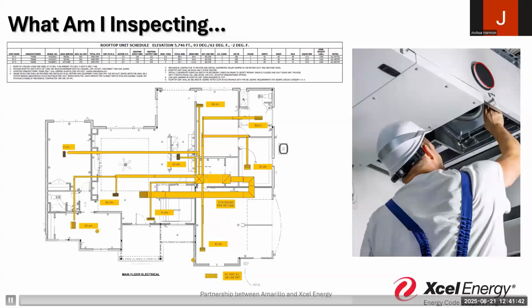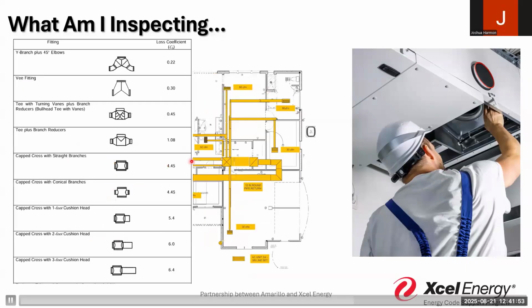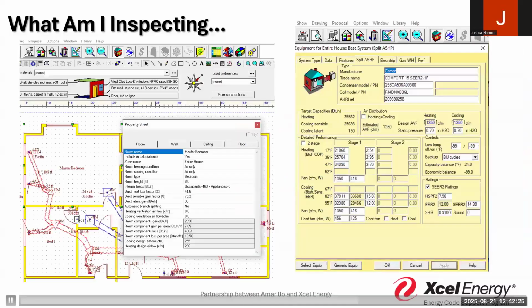It takes time to get that understanding within our designers that I want to know not only the CFMs of air going to each vent in those different rooms, but also what those different fittings, boots, and terminations are going to look like. I can't tell you how many times I'd go out there and think, I know there's supposed to be a T here, is it the right T? Is this the right Y? Is this the right 90? All I know is that the map shows it turns, so that must be the right one. When we think about actual design to a standard like Manual D, that process is a lot more involved than just plugging it in and letting it go.